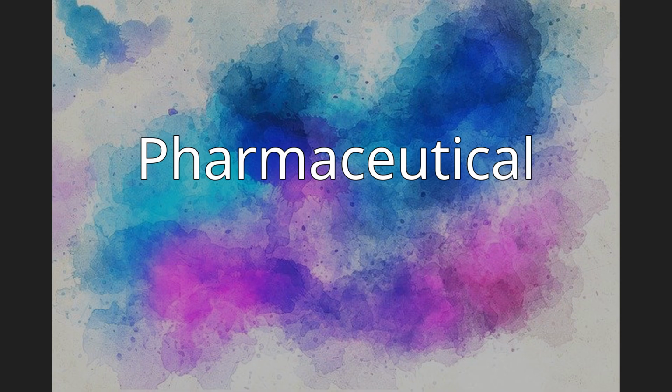Pharmaceutical. Tygon LFL long flex life pump tubing is non-toxic clear tubing with broad chemical resistance. It is often used in product filtration and fermentation and surfactant delivery. Tygon 2275 high purity tubing is a plasticizer-free material that is often used in sterile filling and dispensing systems and diagnostic equipment. This formulation is also considered to have low absorption/adsorption properties, which minimizes the risk of fluid alteration.